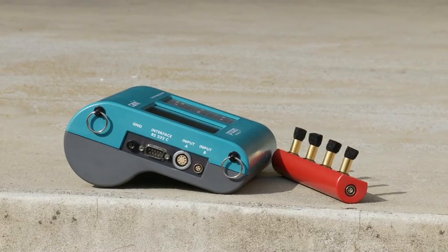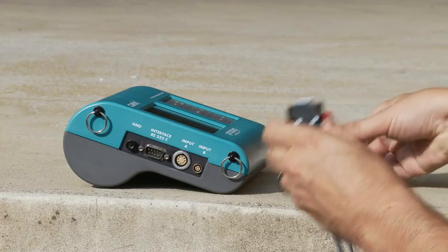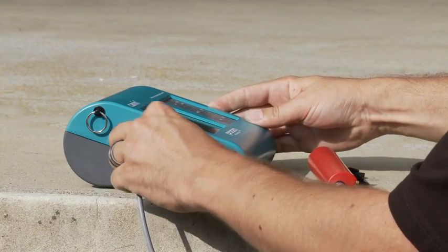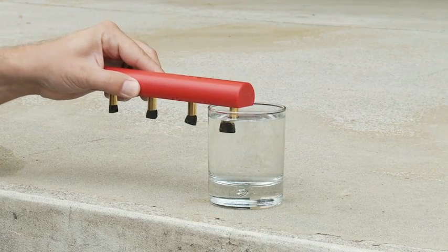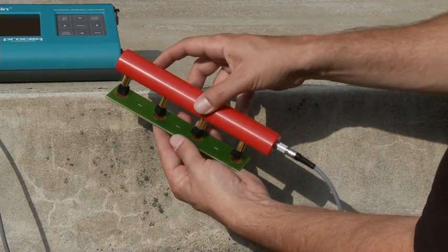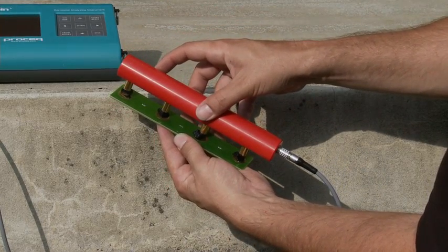To carry out a resistivity measurement, connect the probe with the RS-232 interface of the indicating device. Moisten the 4 foam rubber pads with water. Carry out a functional check by placing the Wenner probe onto the control plate. The reading shown in the actual window should correspond to the value written on the test plate.